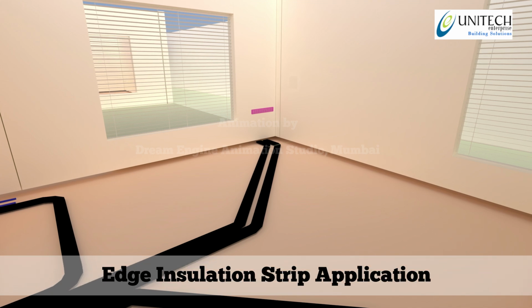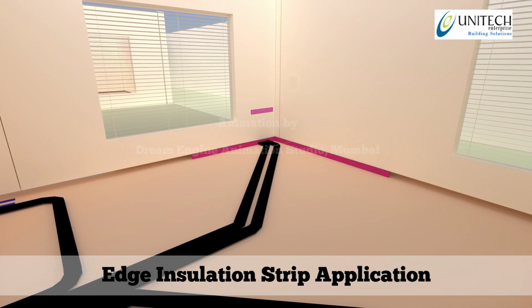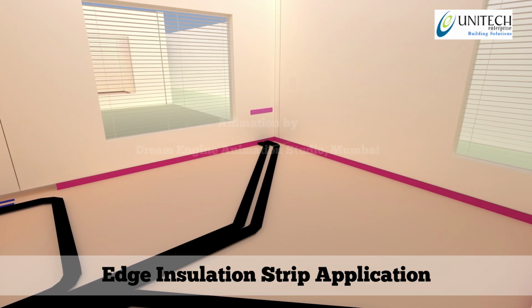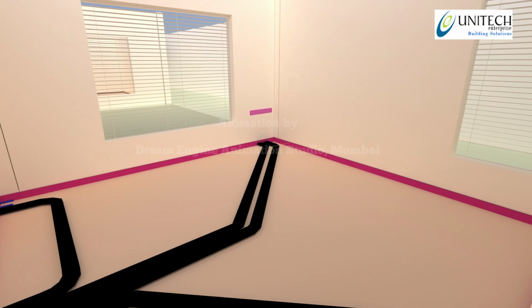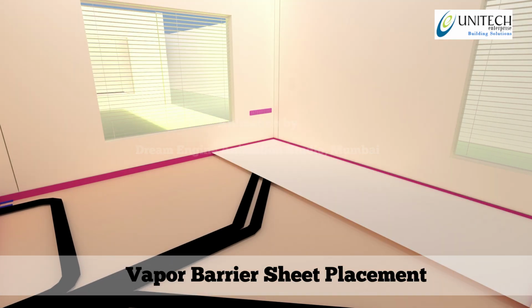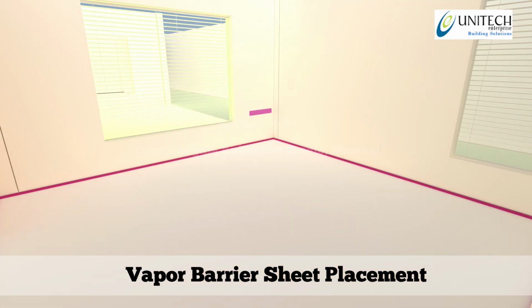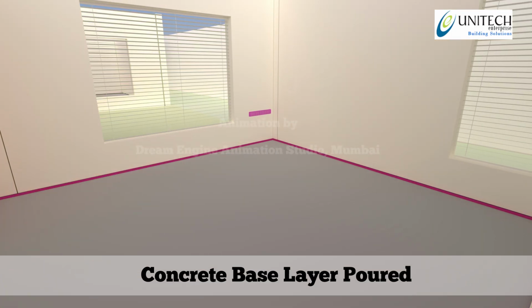Edge insulation strips are then applied around the perimeter to minimize thermal bridging and accommodate floor expansion. A vapor barrier sheet is laid across the floor area, helping protect the system from ground moisture and ensuring long-term performance. Once the preparation layers are complete, a concrete base layer is poured to create a stable foundation.